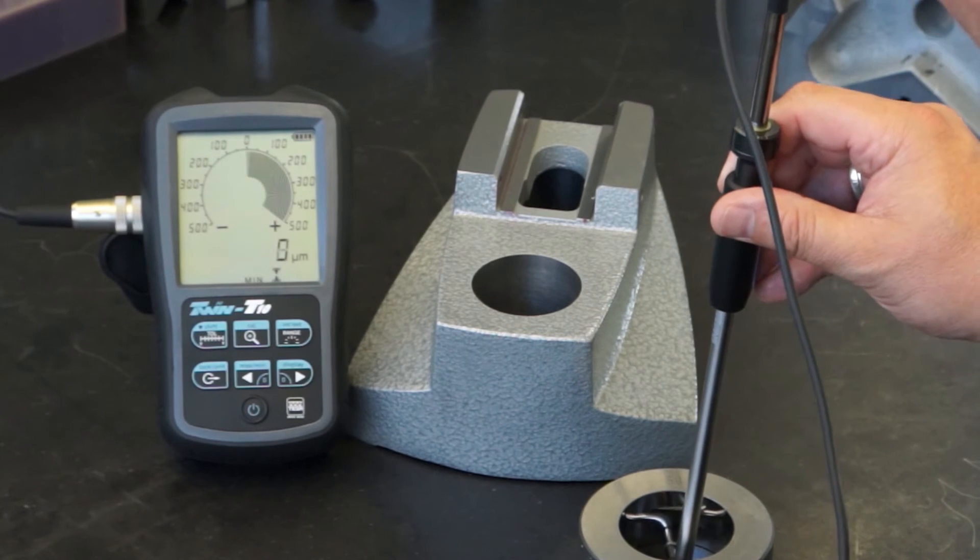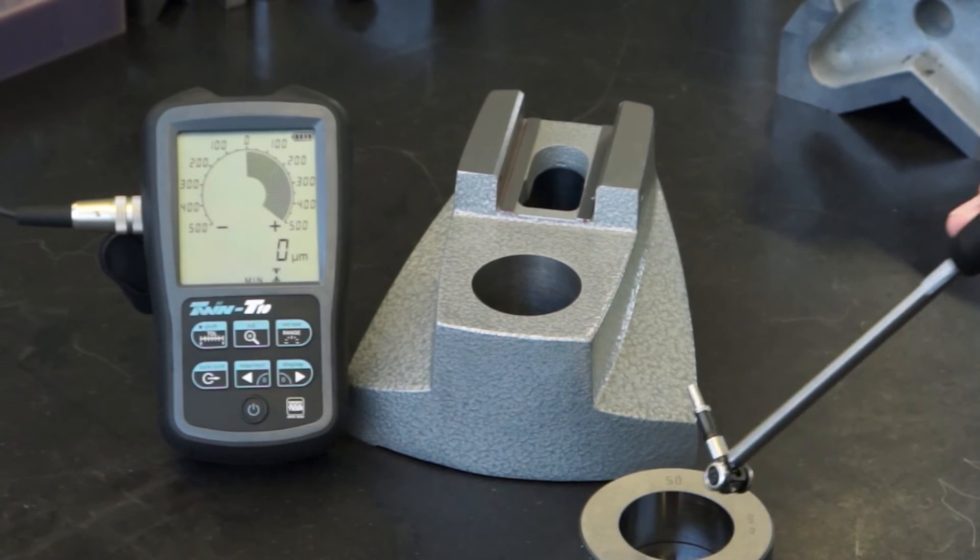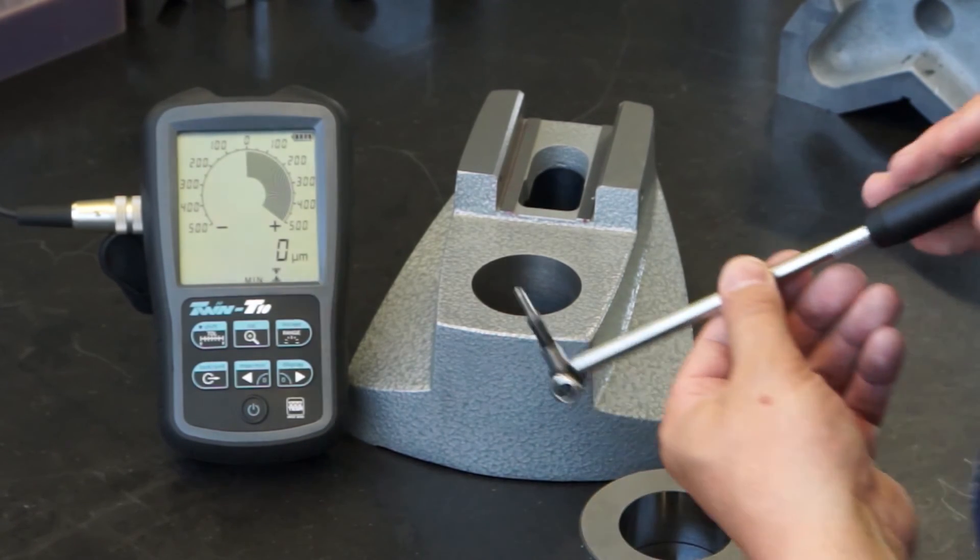The measurement is first done using a setting ring to check that the master value is zero, meaning there is no offset value.